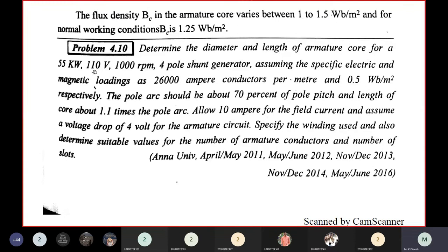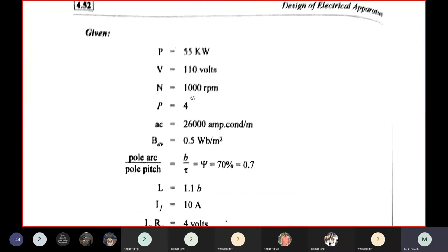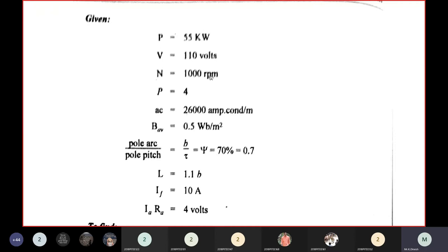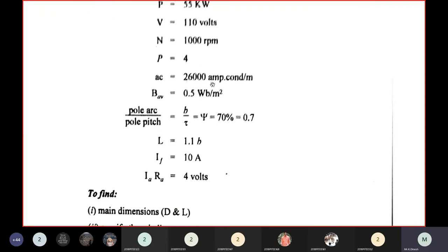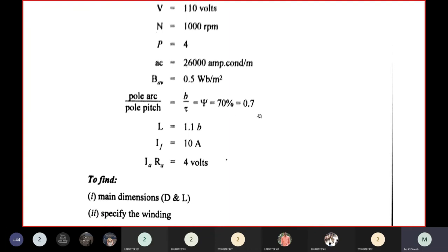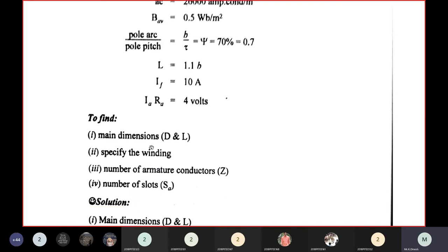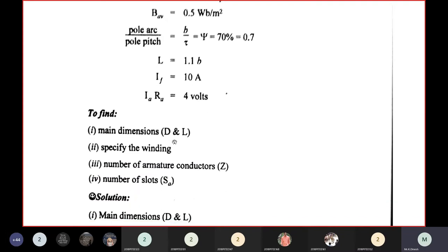Given: power = 55 kW, voltage = 110 V, speed = 1000 rpm, poles = 4, AC = 26,000 A/m, BAV = 0.5 T, pole arc to pole pitch ratio = 0.7, L = 1.1B (pole arc), field current IF = 10 A, armature voltage drop IARA = 4 V. Find: main dimensions D and L, specify the winding, number of conductors Z, and number of slots SA.